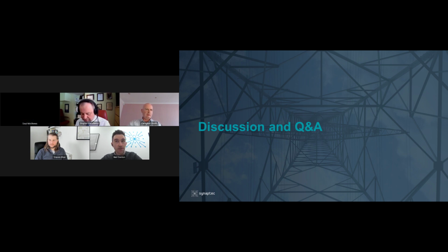Sure. Well, the technology that kind of underpins what we do at Synaptec is called a fiber Bragg grating. So if you want to look that up, that's probably the easiest way to get familiar with it. But fundamentally it's the device that does the encoding of the measurement into that wavelength signal. And Synaptec's IP is in using that for an electrical measurement, but you can also use them for mechanical measurements as well. And as far as our interrogator is concerned, they're all identical. They're all just wavelength signals that are being delivered back to the interrogator in reflection. So the interrogator is basically agnostic as to whether the signal it's receiving is a voltage or a current or a temperature or a strain or a vibration.